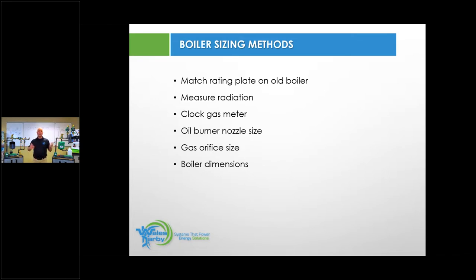It may be right, it may not be right. We didn't do a heat load calculation, we don't know. We can measure the radiation, and that'll tell us how much radiation's in the house. Doesn't tell us if it's the right amount of radiation in the home. It just tells us how much radiation is within the home. And that becomes a really important factor when you're making a boiler choice decision. How much radiation is within the home? If it's over radiated, you can go to a condensing boiler and bring the temperatures down, right? So we can make that condensing boiler condense and run at a higher efficiency.